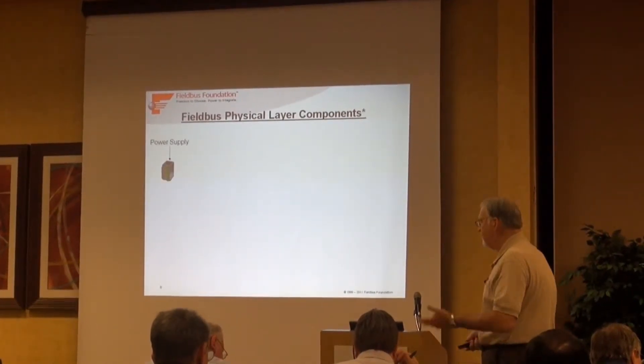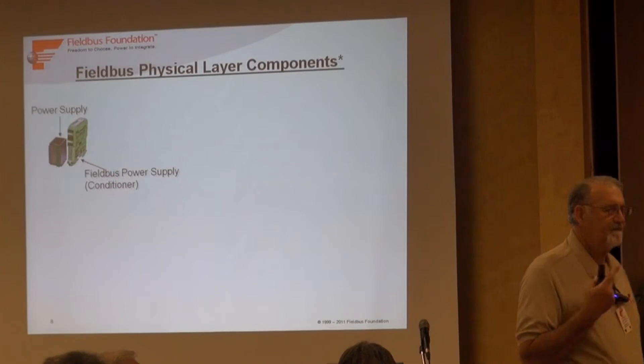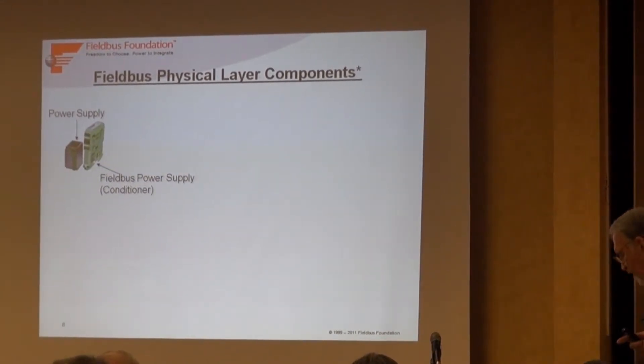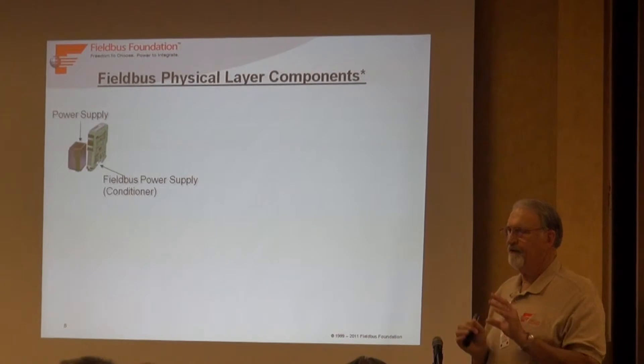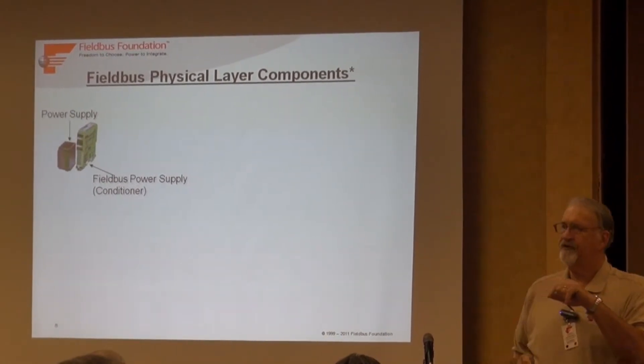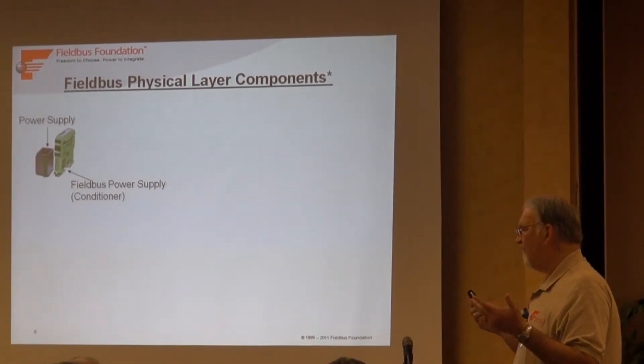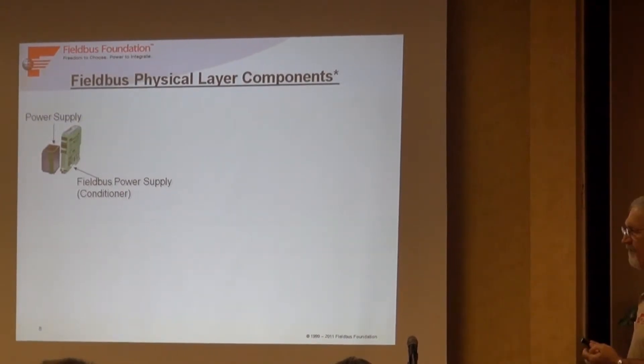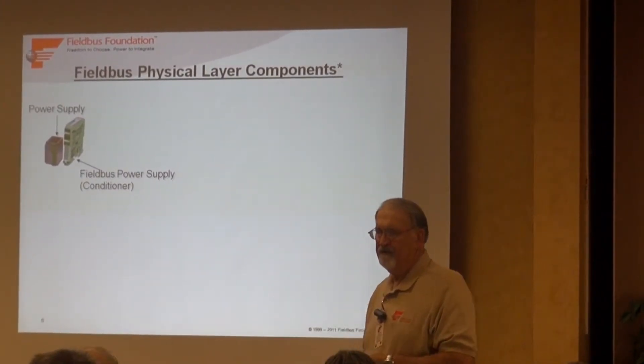So let's build something. You start with a power supply - a regular old power supply - but that feeds a fieldbus power supply. In the old days they were called power conditioners, and they still are. As the technology evolved, they started putting power conditioners on a motherboard, two to four on the same backplane. The problem was you could get noise in between - they weren't isolated, so you could propagate noise from one segment to another. So it became an isolated power conditioner, which we refer to as a fieldbus power supply. There are registered fieldbus power supplies now, so you don't have that propagation problem.